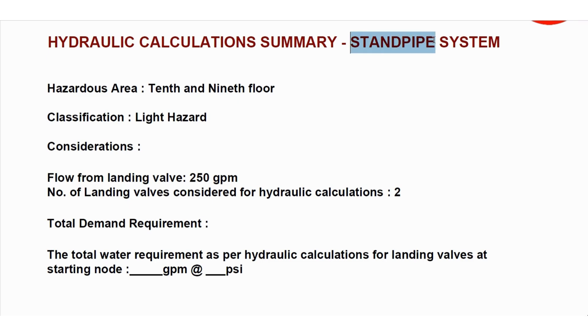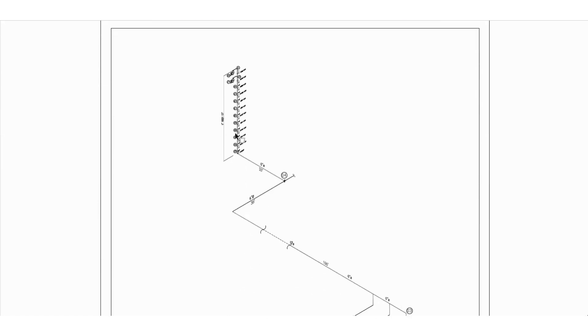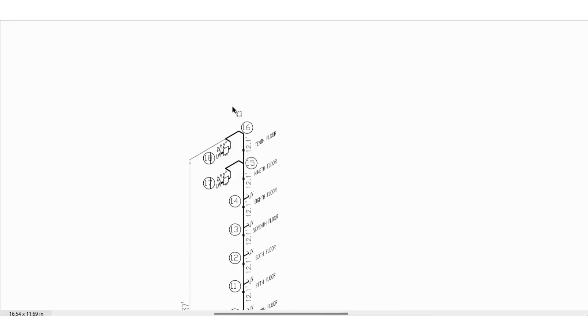Basically when you say standpipe system, it means we are considering the landing valves only. Looking at the summary sheet, the total demand requirement based on the hydraulic calculation for the landing valves will be mentioned in GPM, along with the inflow pressure required at the starting node. As per NFPA 14, we need to consider two remotest landing valves and the landing valve size will be 2.5 inch only. We cannot consider less than 2.5 inch.